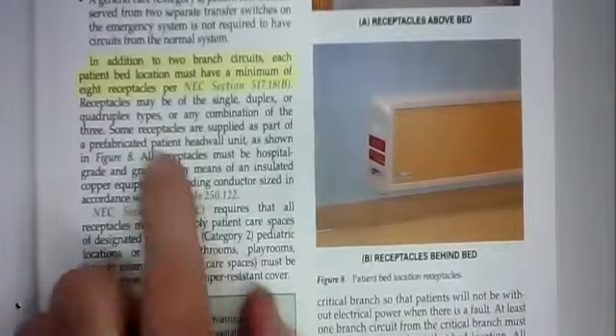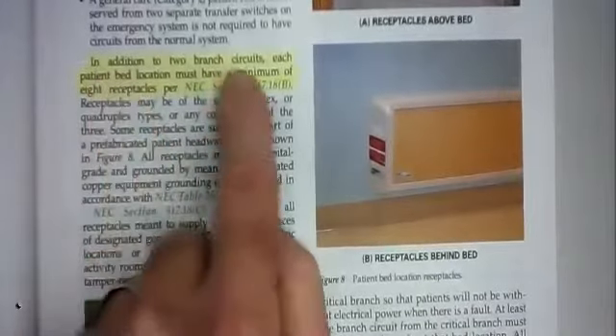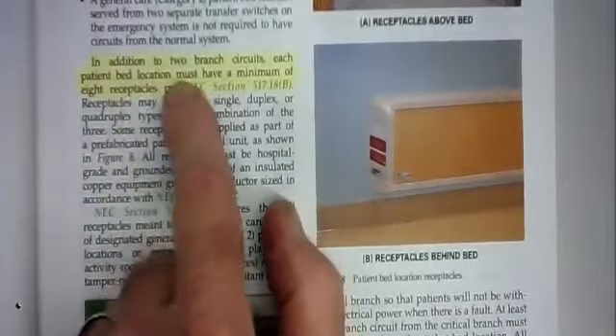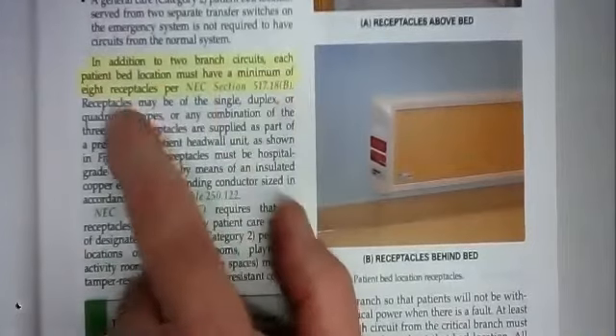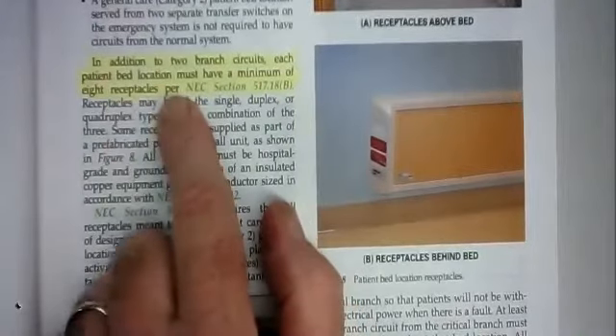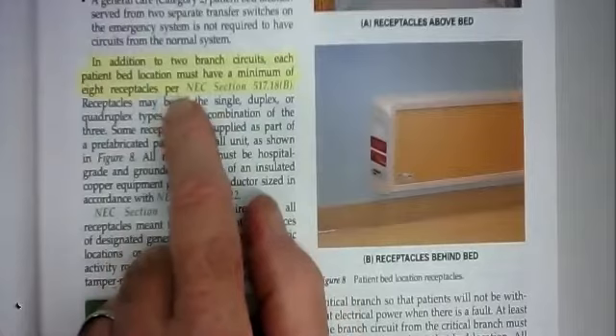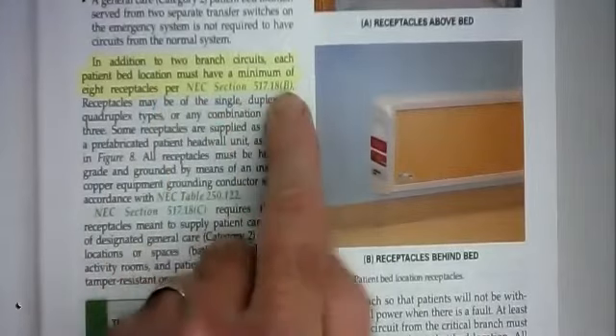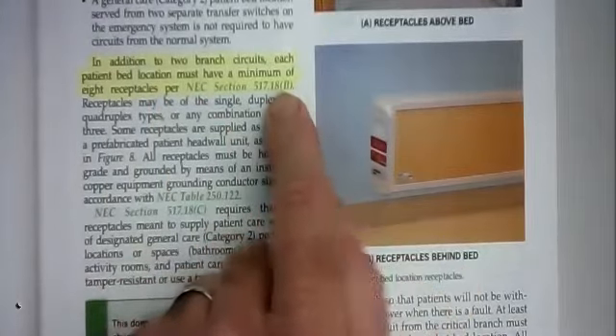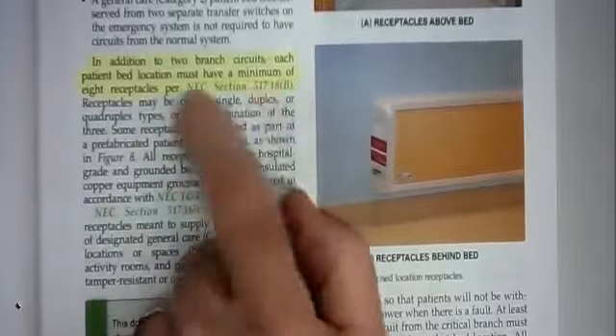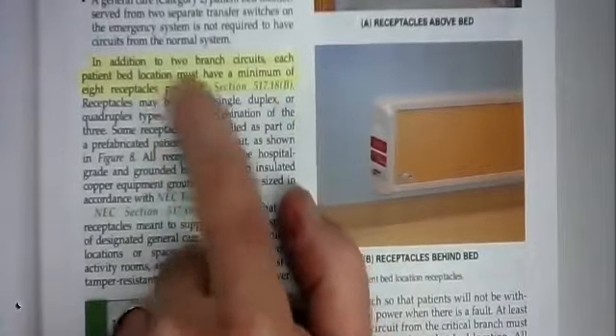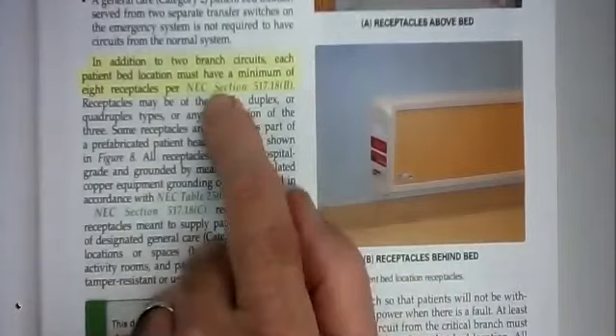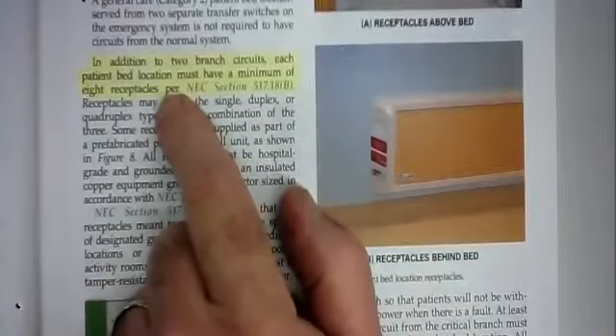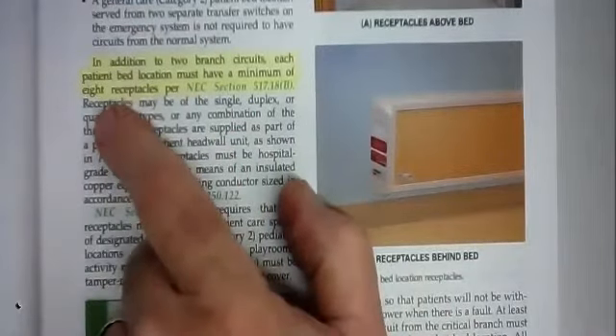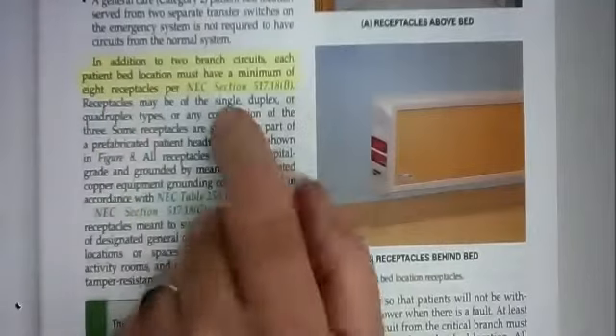Over on page 13, left-hand side, it says, in addition to 2 branch circuits, each patient bed location must have a minimum of 8 receptacles. And this isn't critical care, this is just a bedroom. Per NEC section 517.18(B), if you're spending the night at the hospital in a patient care area, there has to be a minimum of 8 receptacles in that area, and I believe 4 of them have to be on regular power and 4 of them have to be on emergency power.